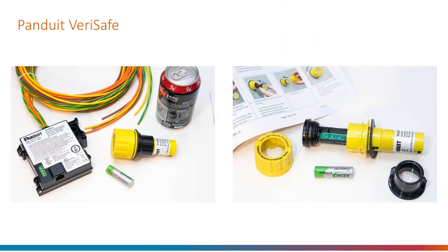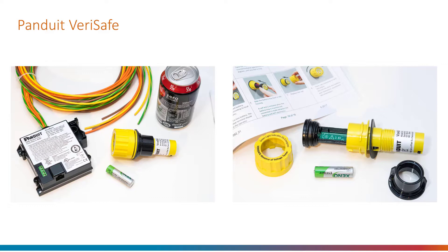This product is designed to automate the procedure by providing a permanently installed test indicator. Basically, the engineer can switch off the mains power and then press the test indicator to confirm that power has been removed. The system will check all phases, but it will also check itself and the wiring as well, in case some connection has worked itself loose.